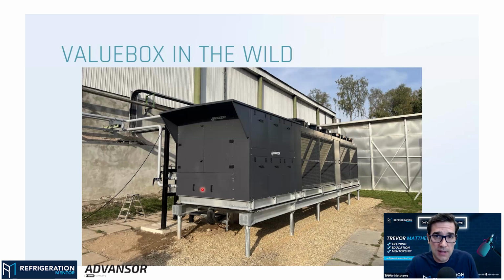So if you get into a heat pump application, now we're dealing with some hydronics that we didn't do before. You got to learn, you got to get the pump. There's going to be a pump curve for that specific pump, depending on the ratings and the horsepower of it. And you got to plot how many gallons per minute, or whatever units you're using, that it can move and flow that specific fluid or whatever the process is.